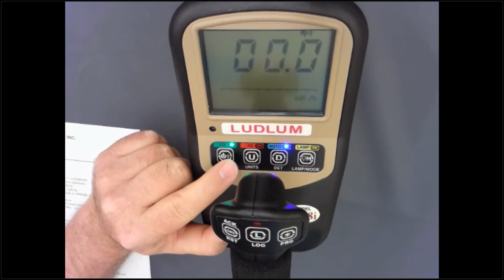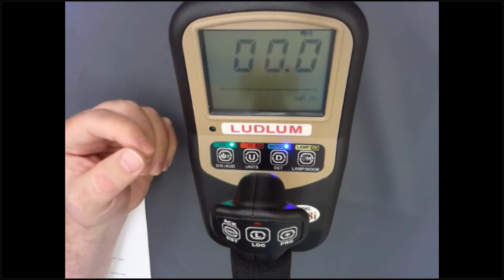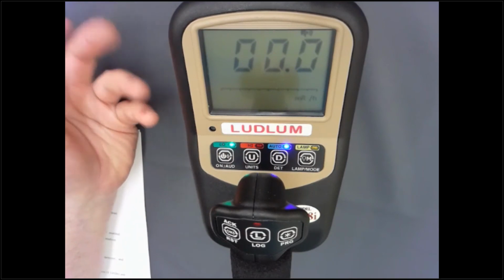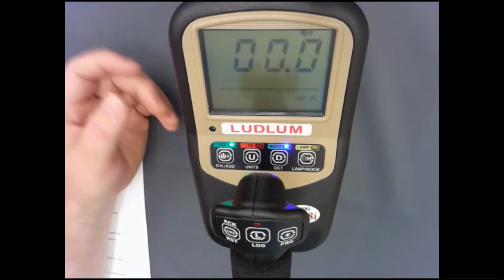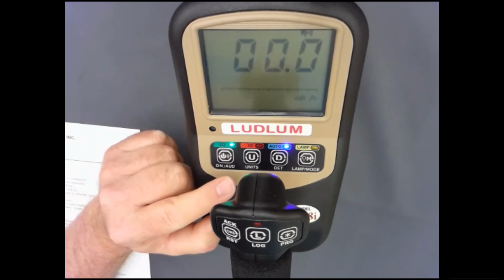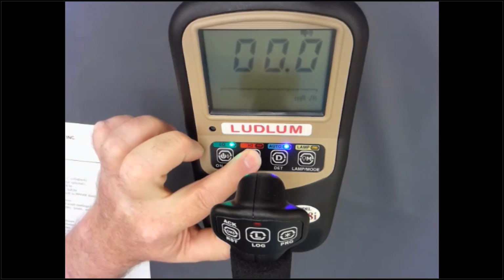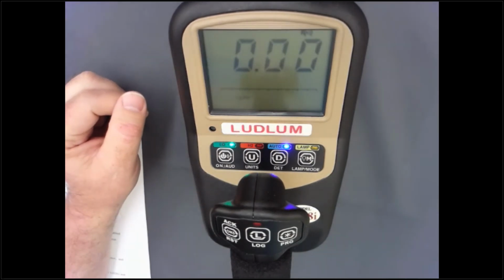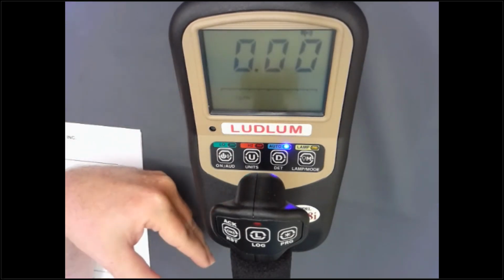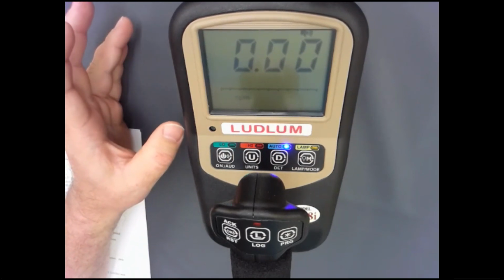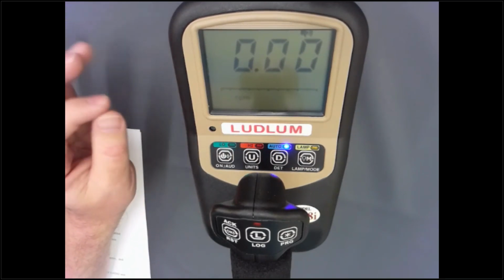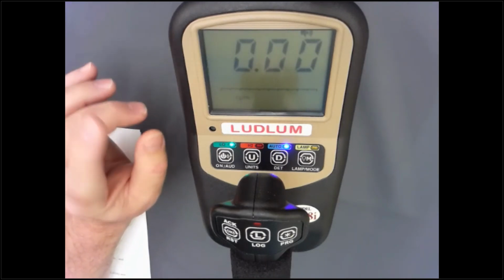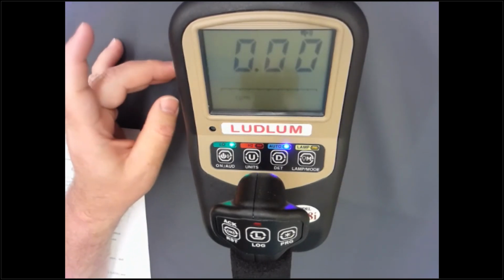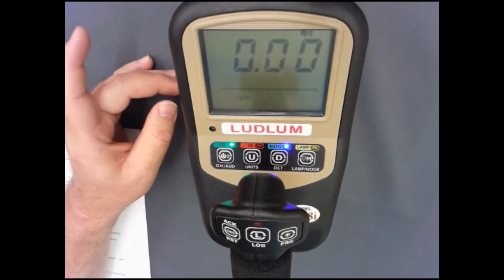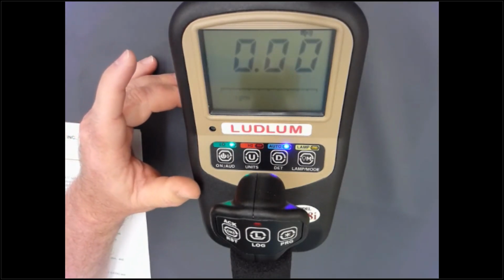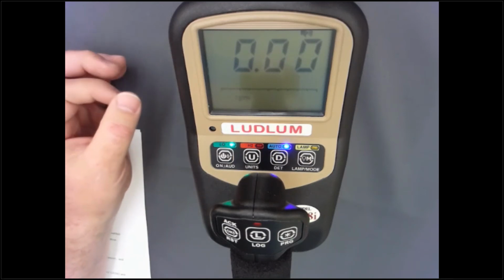The next button to that is the units button, and the units button allows us to change the units for either the external detector or the internal detector, depending upon which one you're viewing. In this case, we're currently looking in MR per hour, but by pressing the units button 1 time, it'll switch over to counts per minute. And we can look at it in either range. So while we're at 0.0 MR per hour to 2 R per hour on the low detector, the low detector will also go from 0 counts per minute up to 10 million counts per minute if it's locked into that range.